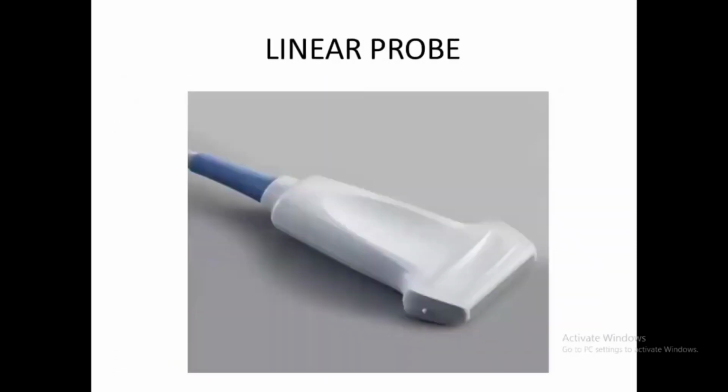Here you can see this probe. In this you can see the layer here. Inside this there will be a layer of piezoelectric crystals. These are the ones which help you to depict the pictures from the human body. If you fail to take care of this probe, then this layer comes out, and when this layer comes out you cannot do scan procedures.